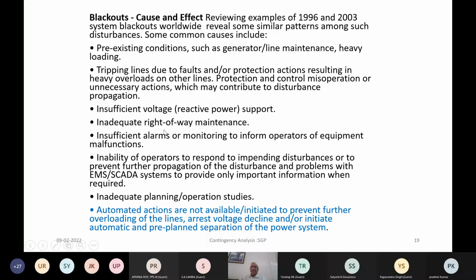Inadequate right of way for maintenance is also one of the reasons for the contingencies of depleting the transmission corridor. Insufficient monitoring of the line loadings, etc. Inability of the operator to respond to impending disturbances, like it happened in the 2012 case also, when the excess power was being drawn under certain 400 kV lines.